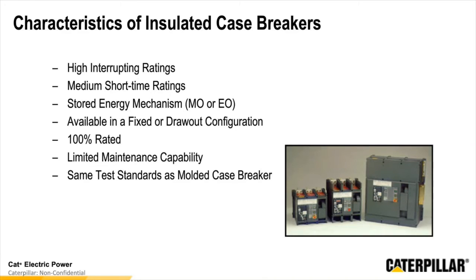So the next breaker is the insulated case circuit breaker. The insulated case breakers typically have a higher interrupt rating. They have a medium to short time rating. These are normally what you're going to find more in the distribution part of the system. They use a stored energy mechanism, either mechanically operated or electrically operated, for being able to open and close.